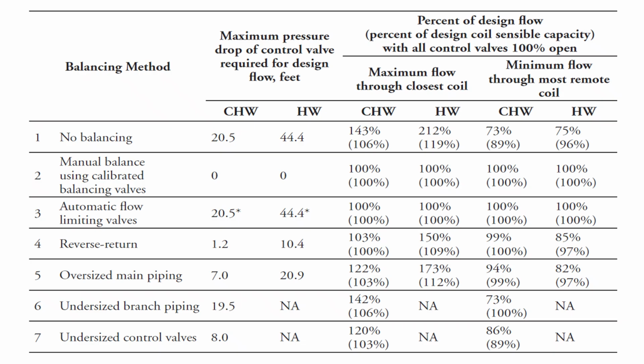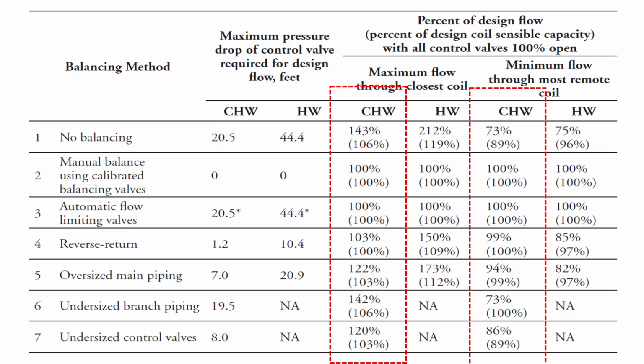To showcase one of the charts wherein all these strategies are mentioned here: you see no balancing, manual balancing, the pressure limiting valve, instead of that the pressure independent valve I had already mentioned, reverse return, oversized main piping, and undersized branches and control valves. Here you will see that there is a maximum pressure drop. Even the pressure strategies like the manual balancing valve, the limiting valve or the reverse return, these three methodologies ensure I'm getting 100% of the flow balance at the maximum flow and the minimum flow. But there is an increase in the pressure drop. So the pressure drop at the chilled water you can see for all of these. So that's how the pressure independent balancing valves take an edge in ensuring the efficient operation of the chiller plant.